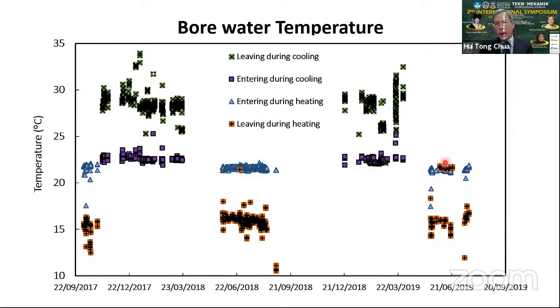The very fact that the groundwater heat pump operates in both heating and cooling is also very good for the groundwater system, because there's no net extraction or net dumping of heat, in a sense. In this case, we are dumping heat during the summer period into the groundwater system, which slowly diffuses to the sea. But come winter, we are dumping colder water back into the same aquifer, and that repeats in the following year as well. So in a sense, this hopefully reduces the environmental impact on our very precious groundwater asset.